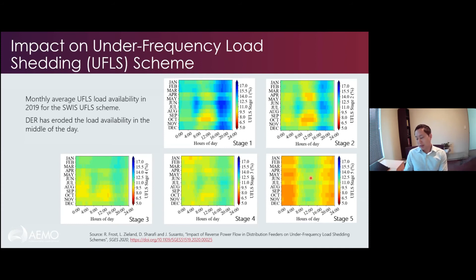So the obvious thing we've done, well, Western Power have done, is swap a couple of these feeders out from stage 5 into stages 1 and 2. That's really improved UFLS availability. On a cloudy winter day it doesn't matter much, the original and rebalanced versions are both around target, but on sunny spring days you see real erosion in the middle of the day. Once rebalanced, it's back up to the 15% mark, which is good.